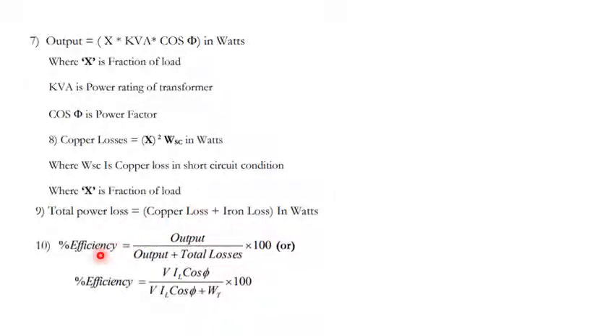Then finally the percentage efficiency can be calculated by using this formula: output divided by output plus total losses. That means output divided by input, and input we can write as output plus total losses. Then you can write percentage efficiency is equal to V into IL cos phi divided by V into IL cos phi plus WT. V IL cos phi is nothing but the output. The total loss is WT, which is nothing but WI plus WSC.